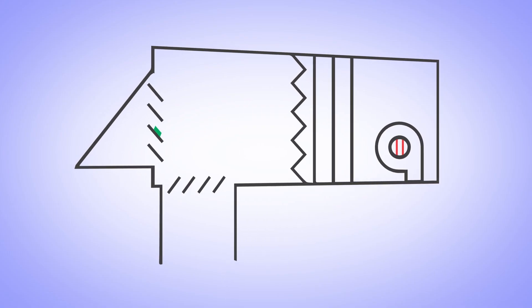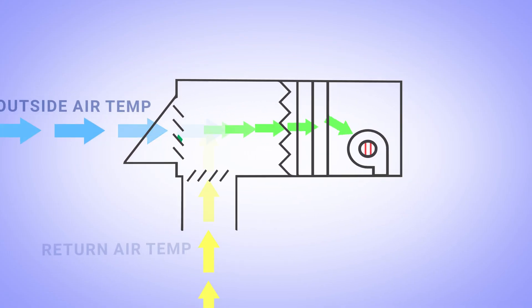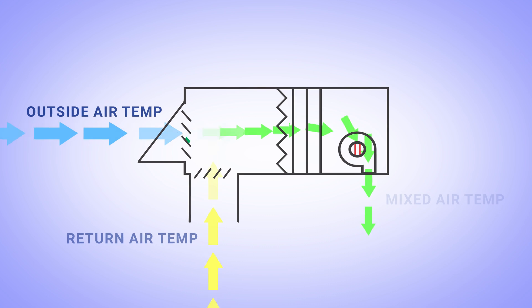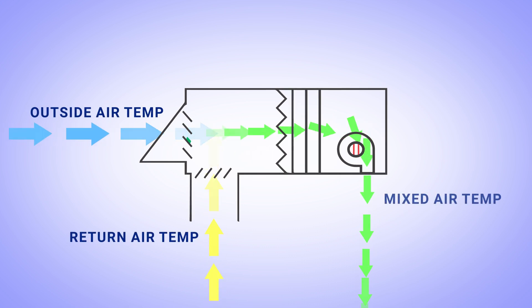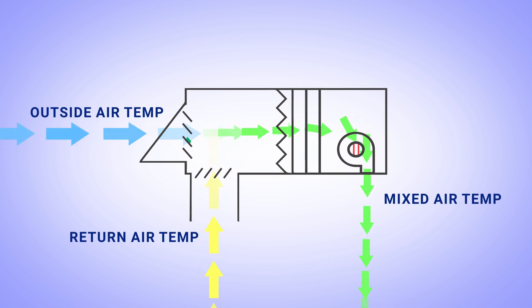During learned mode, the damper is positioned at several known points. At each point, the airflow, outside return, and mixed air temperature readings are allowed to stabilize before being sampled and averaged. The learned mode sequence requires a minimum delta T between outside and return air to ensure best accuracy. Table data may also be manually input if the desired delta T isn't available or if air balancer data is preferred.